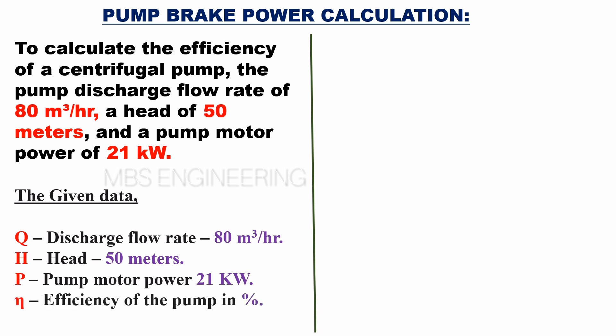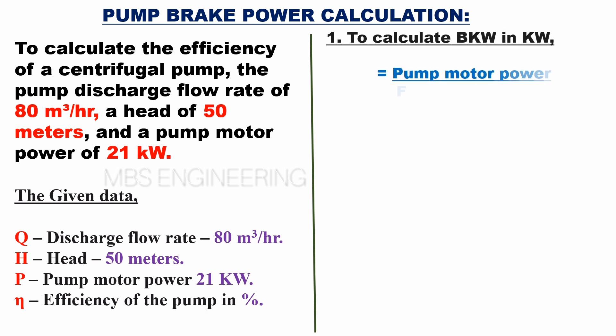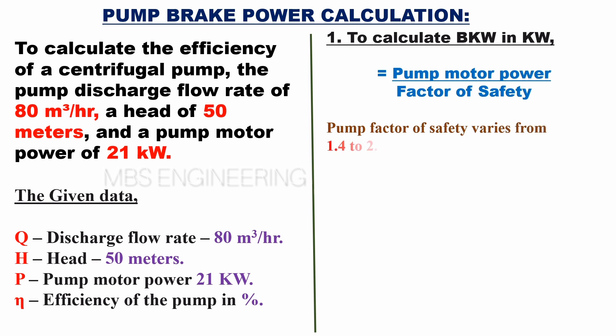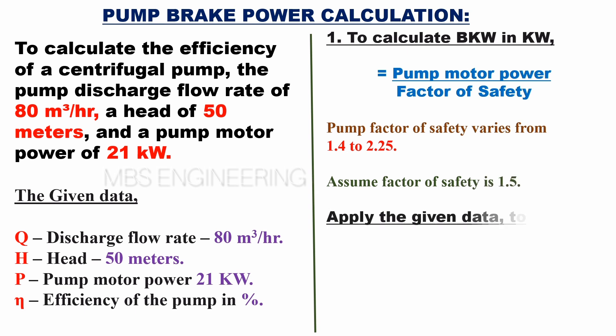We will calculate brake kilowatt in kilowatts. Brake kilowatt equals pump motor power divided by factor of safety. The pump factor of safety varies from 1.4 to 2.25 — assume the factor of safety is 1.5. Applying the given data: BKW equals 21 divided by 1.5. Therefore, the obtained brake kilowatts is 14 kilowatts.